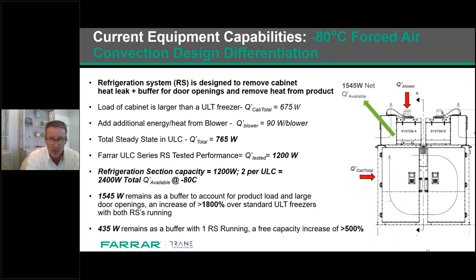If you look at the slide on the right-hand side, you see two refrigeration systems, system A and system B. And this is why I'm mentioning 483 watts with one refrigeration system operating. Having the second one operating would roughly bring it to 808 watts. Keep in mind, we added the fan energy for the second system, right? So that's why we have 808 watts. Each of the two air convection refrigeration systems is designed to remove 1200 watts from the space. Thus the reserve capacity is two times 1200 watts minus 808 watts. That's equal to 1,592 watts. And I apologize, I have 1,545 listed here. But that's the system, right?